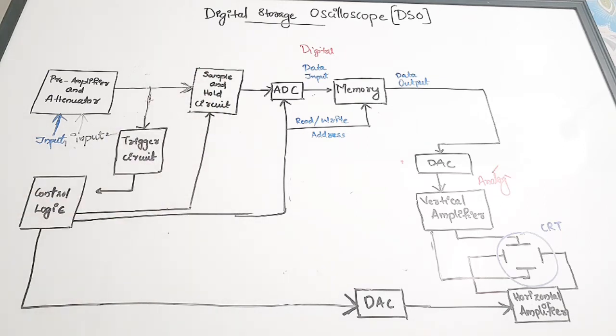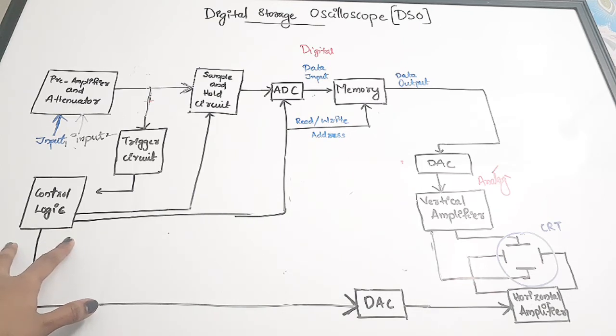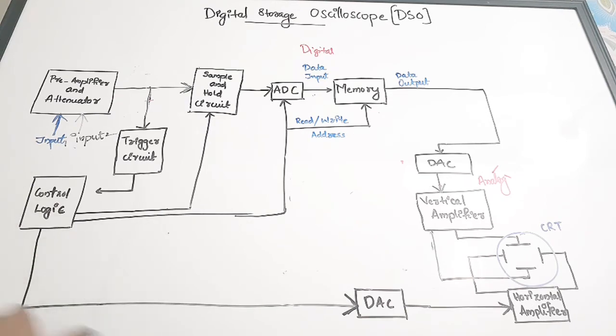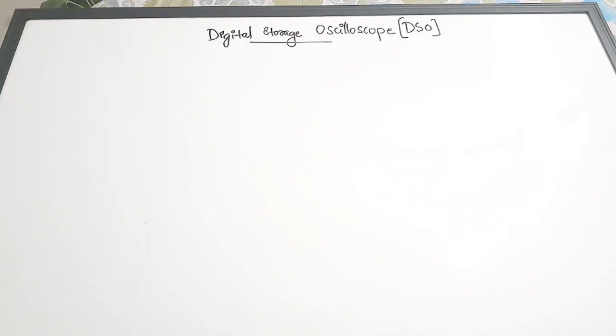This is all about the digital storage oscilloscope. We have discussed all the basic blocks - how the signal gets stored, how it gets digitized, how the time base is generated. The control logic can be a microcontroller or microprocessor which generates the time base. Next we are going to see some important questions from the DSO.